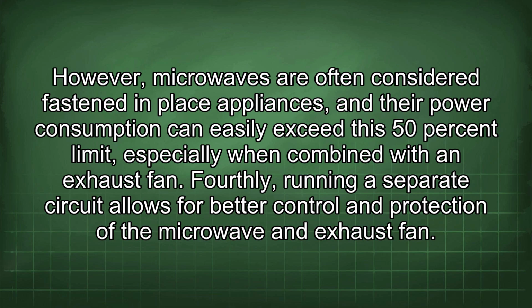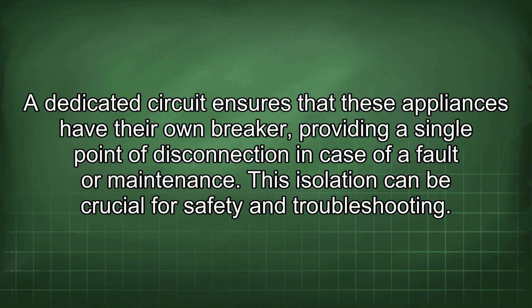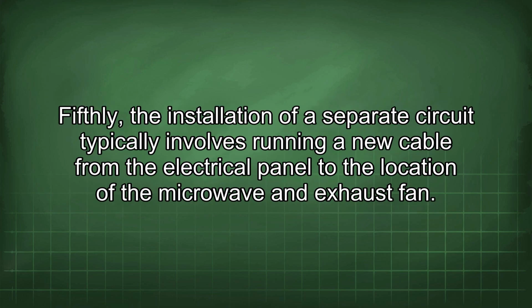Fourthly, running a separate circuit allows for better control and protection of the microwave and exhaust fan. A dedicated circuit ensures that these appliances have their own breaker, providing a single point of disconnection in case of a fault or maintenance. This isolation can be crucial for safety and troubleshooting. Fifthly, the installation of a separate circuit typically involves running a new cable from the electrical panel to the location of the microwave and exhaust fan.